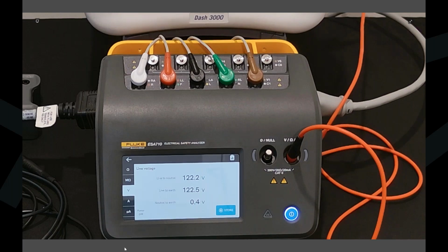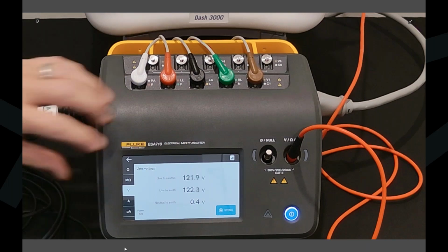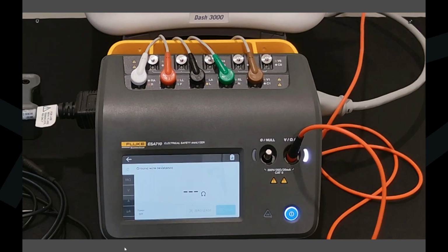If one of the biomeds out there is doing some troubleshooting, and it could possibly be a battery issue, you want to validate if you're having a battery issue or a power issue - you just plug it into your source, go right to measurement, and there you can validate that your power is good. And there's your standard protective earth resistance, and I have it up to device under test.